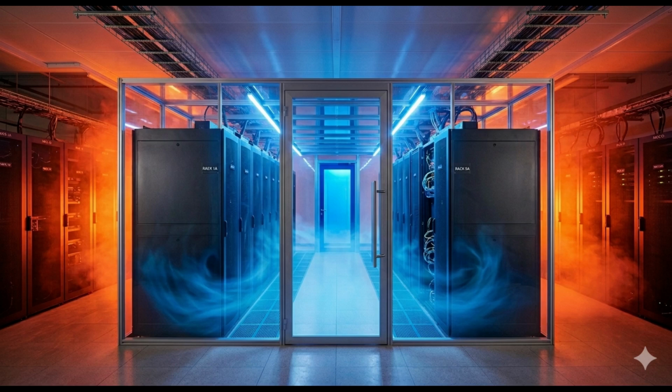Because if a hot aisle isn't contained, that hot exhaust air just rolls right over the top of the cabinets and gets sucked back into the cold server intakes. Which completely degrades your delta T. By sealing the airstreams, containment guarantees that the air returning to the cooling unit is as hot as structurally possible. And going back to the heat balance formula, higher return temperature means higher delta T, which means lower fan speed and massive energy savings.